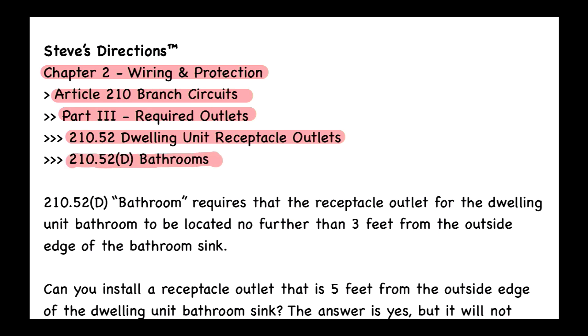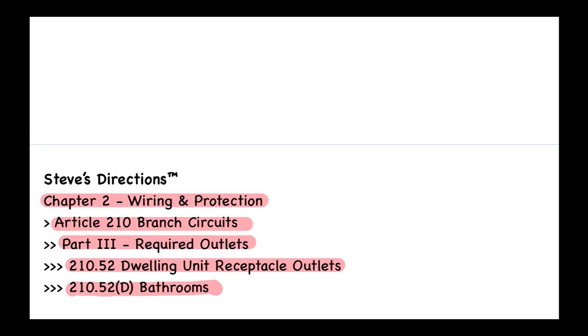Let's look at 210.52(D) together. It says 'at least one receptacle outlet' — and it's important to note that a receptacle outlet refers to the box, not the receptacle device itself. Many electricians confuse a receptacle with a receptacle outlet. It's a slight but important difference. The code states at least one receptacle outlet shall be installed in bathrooms.